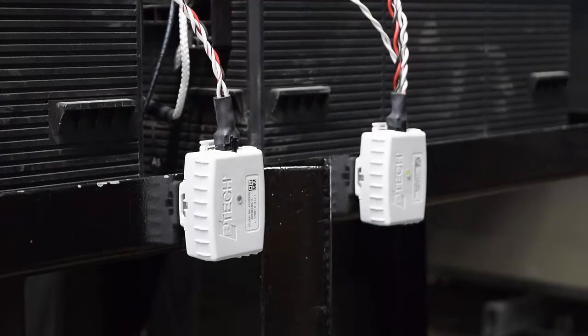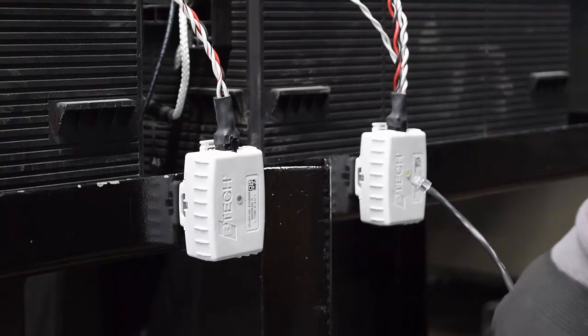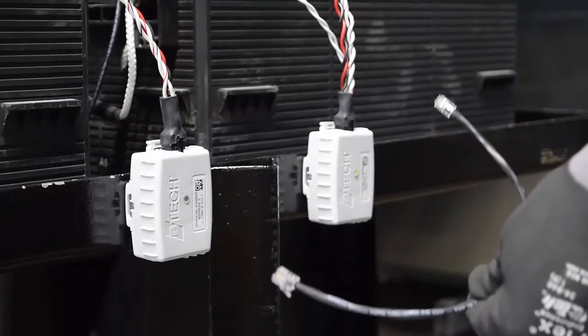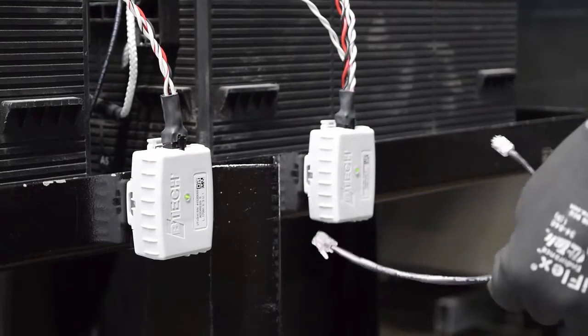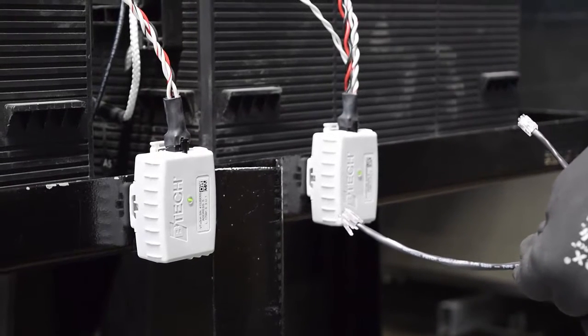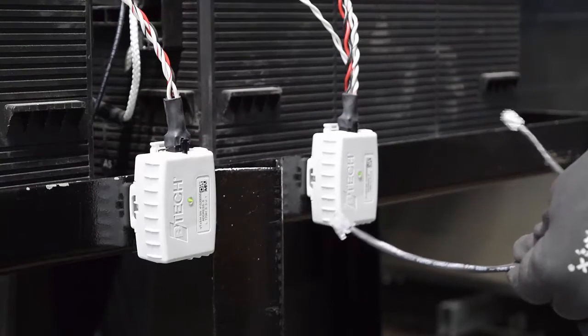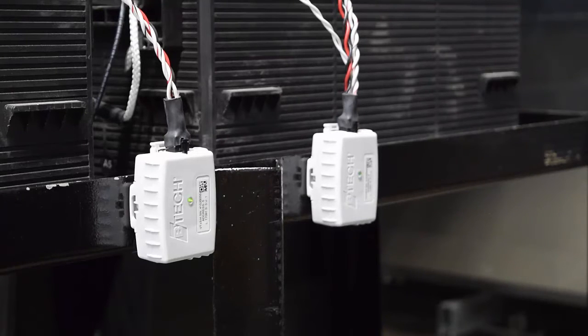The CellQ1 communicates with the VTZ3 and BVI3 modules using a daisy chain communication cable called the S-Bus. The cables get attached from the CellQ1 controller to the first module, then first to the second, and so on, until all the modules are connected. The order of S-Bus connection does not matter as long as all the modules are connected.